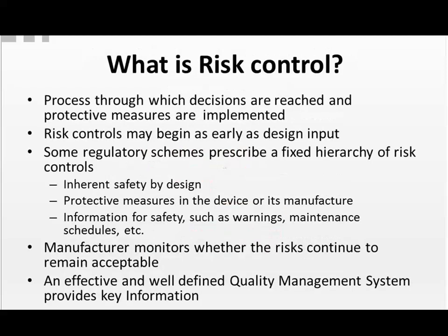Now, let me take a moment and clarify what is meant by risk control. Risk control is the process through which decisions are reached and protective measures are implemented for reducing or maintaining risk within the specified risk level. Now, these actions are intended to eliminate or reduce each risk to meet the previously determined risk acceptability criteria. Now, one or more risk control measures may be incorporated during this step. Risk controls may begin as early as design input and continue over the medical device's lifetime.